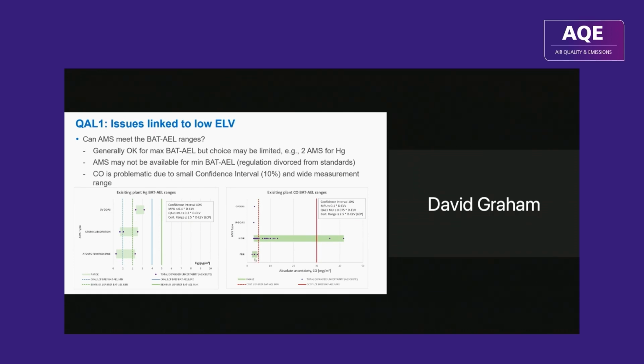So there might be, I don't think there are any instruments that can do that. Certainly by the time you get down to 5, none of the instruments can meet that. So CO is also difficult because although it's almost zero during normal operation, it's very high during startup. So there's a wide measurement range requirement.